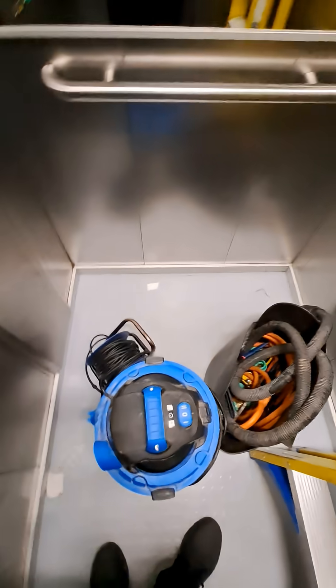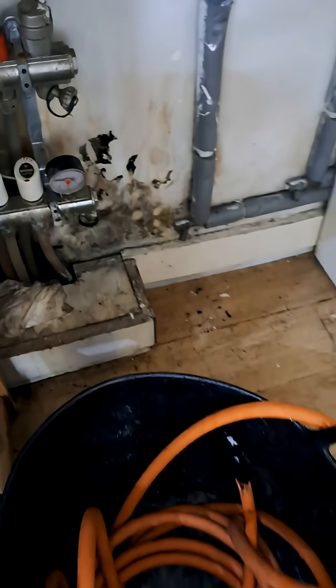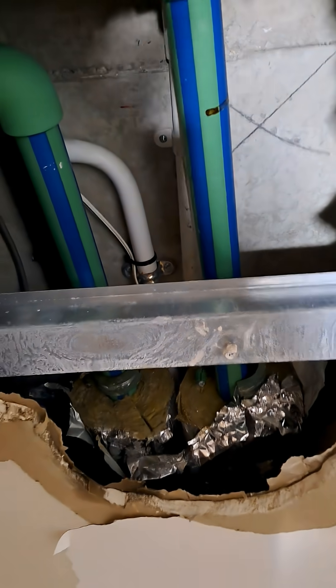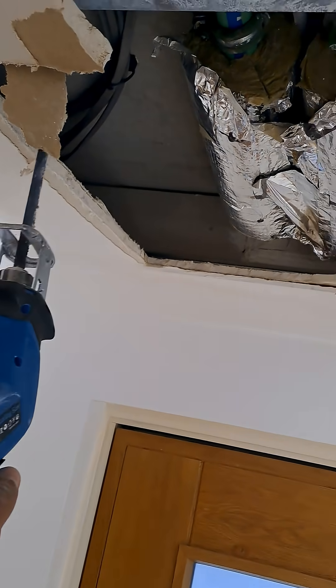I may have to bring a lot of things up to get this done. The HIU also had a leak on it, which they were catching in a bowl. I had to let all the residents know the water was going to be off — there were about seven residents affected, because there's no individual isolation; it's a shared isolation. Here's the Aquatherm, or thermal fusion, iron.